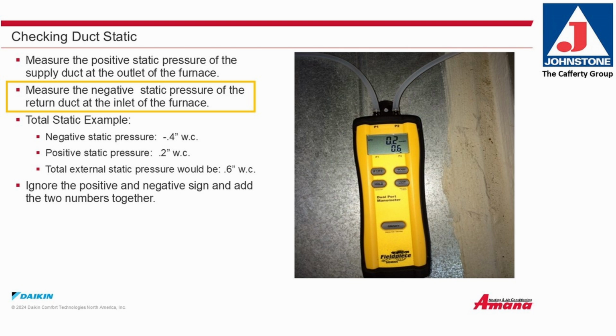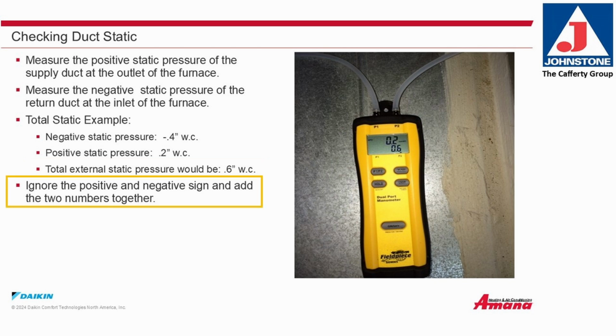Total static examples: negative static pressure, negative 0.4 inches of water column. Positive static pressure, 0.2 inches of water column. Total external static pressure would be 0.6 inches water column. Ignore the positive and negative sign and add the two numbers together.